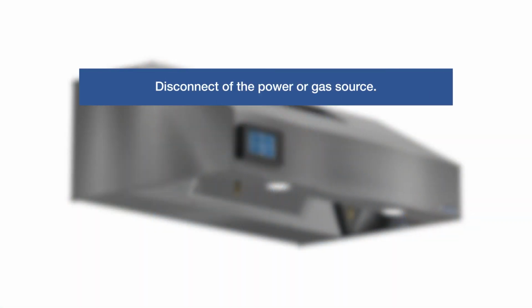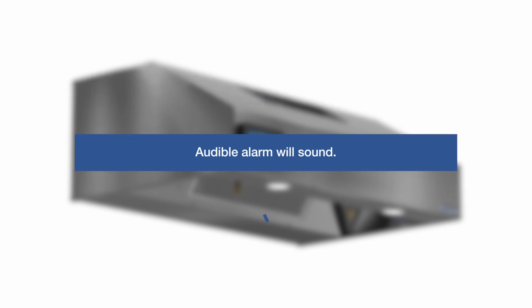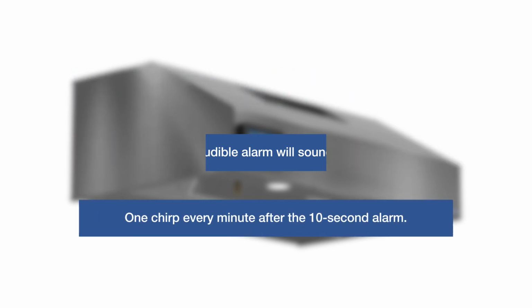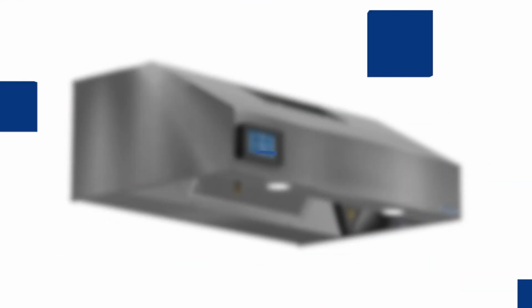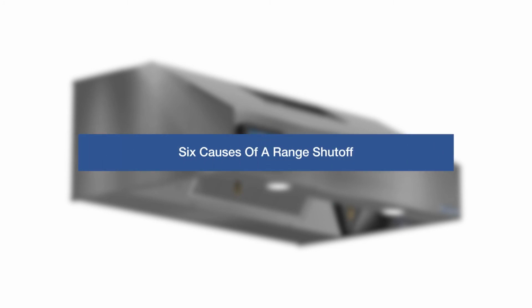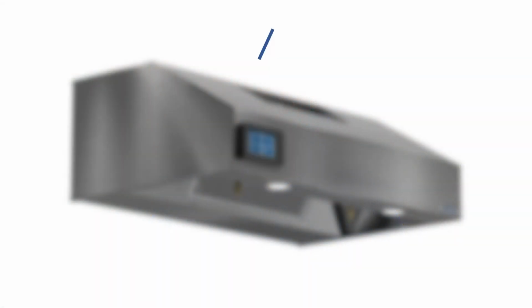A range shutoff sequence will consist of a disconnect of the power or gas source from the appliance, an audible alarm tone, then, after the 10-second alarm, the unit will begin to issue 1 chirp every minute to alert users that the fire suppression system needs to be serviced. There are 6 things that can lead to a range shutoff occurring. Let's discuss these, starting with the most likely cause.